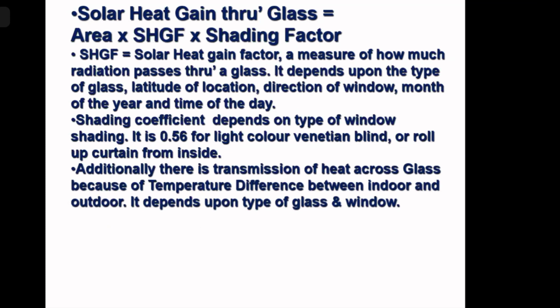Additionally, there is transmission. I said, so far the solar heat gain through glass is area into solar heat gain factor into shading factor. This is the direct solar radiation which is coming inside. Additionally, like other building material, walls and roofs, the glass window will also become hot and heat will come inside because of that. So that also has to be added. So how is that? Let us see. Next.